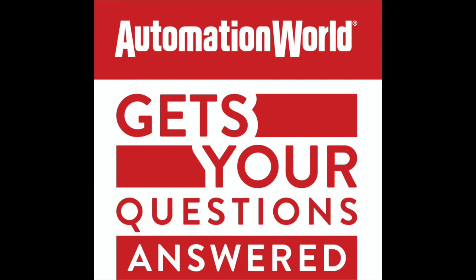All right, well, let's get started, right from the core of it. Let's explain mean time to repair. What does this mean? Sure. So this is one of those acronyms that once you break it down, it's kind of self-explanatory, right? It is essentially the average time it takes to get an asset back up and running once it's gone down. So if your case packer goes down at 12 o'clock and you get it back up and running at 12:30, that took 30 minutes to repair. That's your time to repair. You average all of those downtime periods together over a certain time span, and that is your mean time to repair over that time.